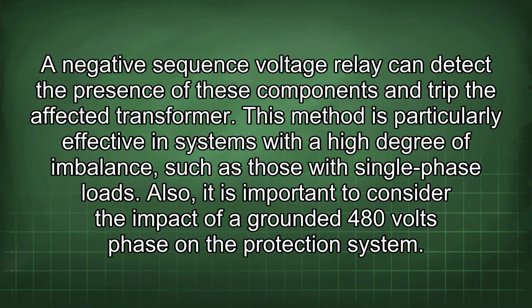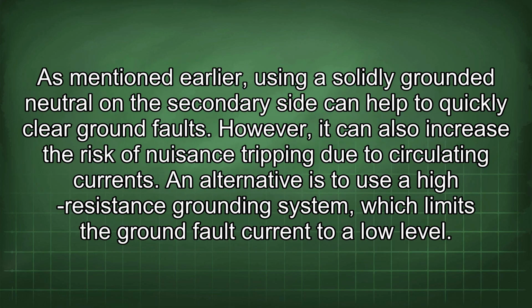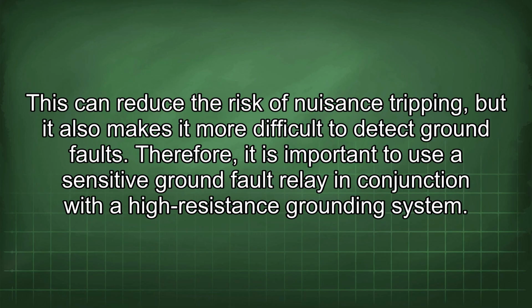Also, it is important to consider the impact of a grounded 480-volt phase on the protection system. As mentioned earlier, using a solidly grounded neutral on the secondary side can help to quickly clear ground faults. However, it can also increase the risk of nuisance tripping due to circulating currents. An alternative is to use a high resistance grounding system, which limits the ground fault current to a low level. This can reduce the risk of nuisance tripping, but it also makes it more difficult to detect ground faults. Therefore, it is important to use a sensitive ground fault relay in conjunction with a high resistance grounding system.